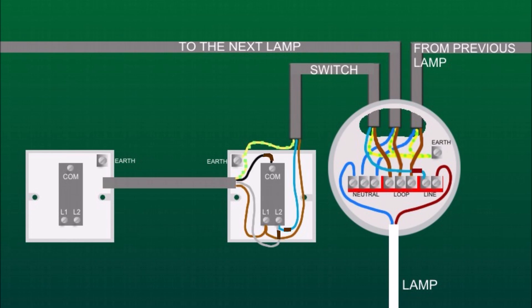At the second switch we do the same: colors to the same terminals as at the first switch. Earth wire goes to earth terminal, brown to L1, gray to L2, and the black wire goes to COM terminal.